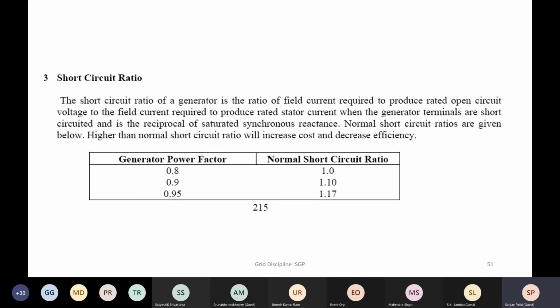These are the typical short circuit ratios for hydro machines. For a thermal machine, these ratios will be less, 0.4 or 0.45, etc. Now, the short circuit ratio is the inverse of reactance, and this synchronous reactance is based on the diameter of the bore of the generator stator winding, the diameter of the rotor winding, and the resultant air gap, because that is what will decide the field current requirement. Depending on the air gap, how much field current needs to be pushed for a given air gap flux density, that is how the size of the field winding gets decided.